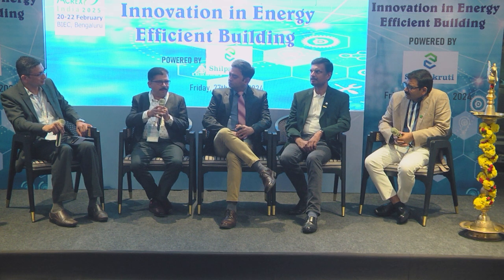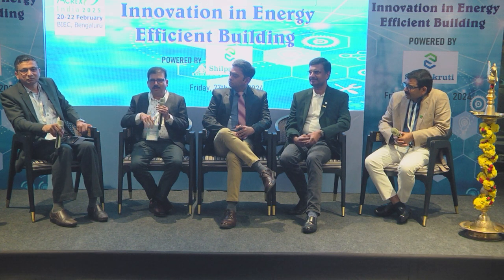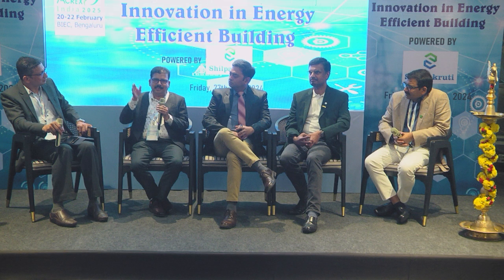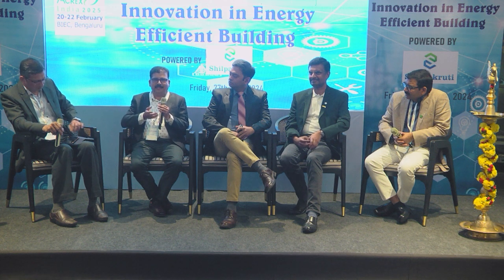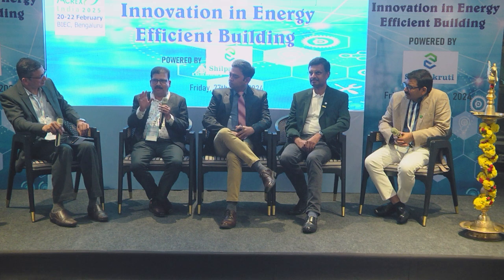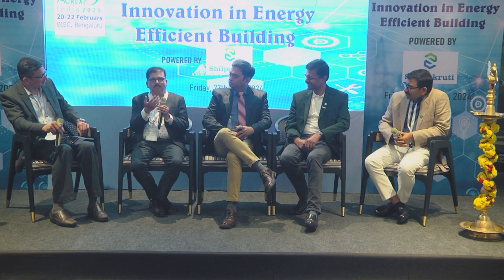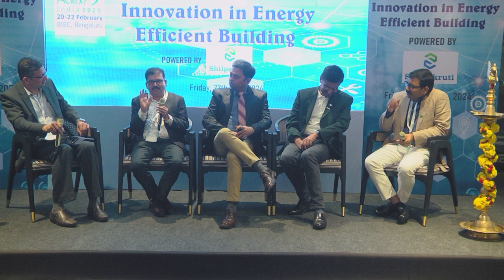Just selecting a pump and connecting it with a VFD will not work. You have to select properly, because when the flow rate comes down, the head also comes down. So the last edge will not get the water flow. Then what is the use of having so much PLC, VFD, everything? The maintenance engineer goes and switches on another pump manually and comes back, so the whole purpose of your energy efficiency is gone to waste.